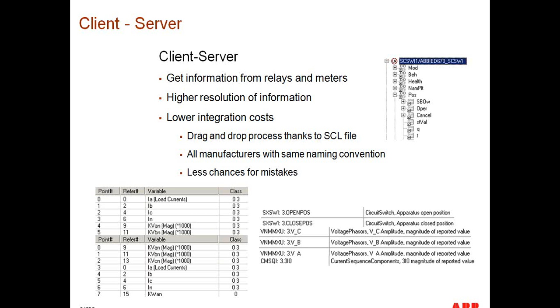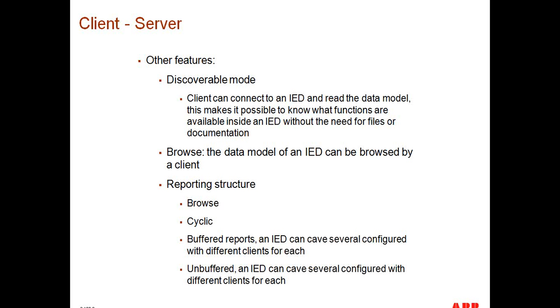From a gateway or HMI engineering perspective, a big part of engineering a system is programming the information that I'm going to fetch from the devices attached to the system. Well, in IEC 61850, populating that list is just as easy as drag and dropping that file, which contains all the information that is enabled inside that particular device. That's why this is so much more efficient to engineer. It's not a text file, it's not a Word file, it's not an Excel spreadsheet. It's a standard XML-based file that contains the capabilities or the template information of a device.